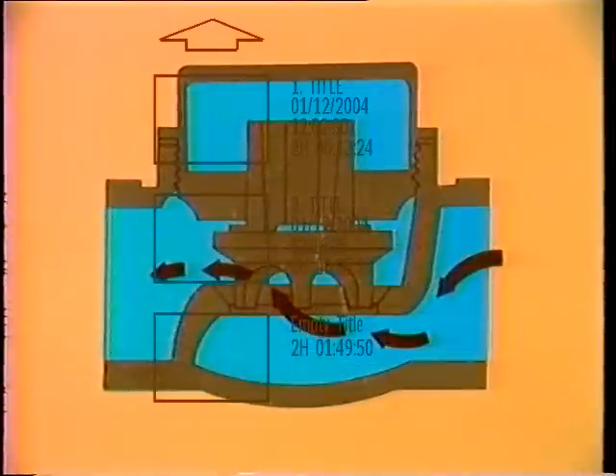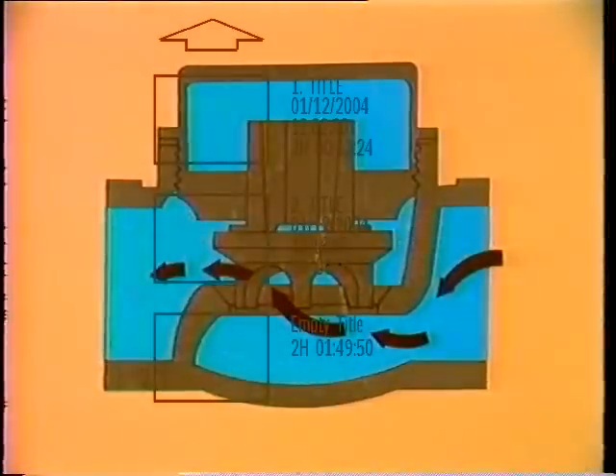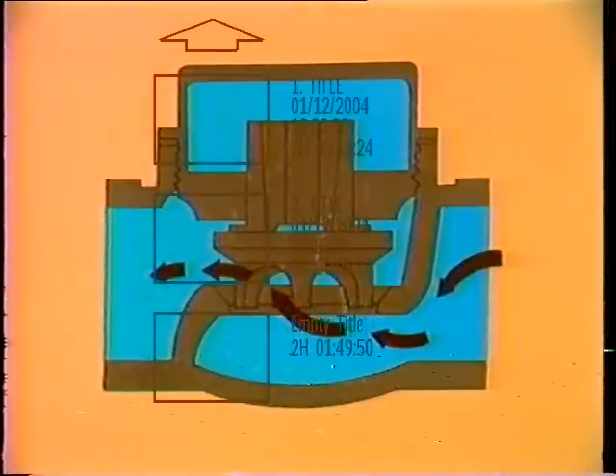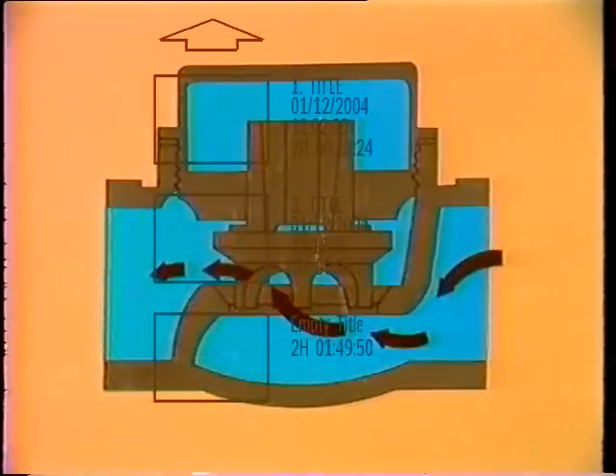The disc on a lift check valve is not pivoted by an arm — it is lifted when system pressure is greater than the weight of the disc, which permits flow through the valve. Guides attached to the disc keep it in position and prevent the disc from cocking or jamming against the seat. Lift check valves are well suited for service in systems with a fluctuating flow such as steam, air, or gases. The slamming does not affect them as it does the swing checks.